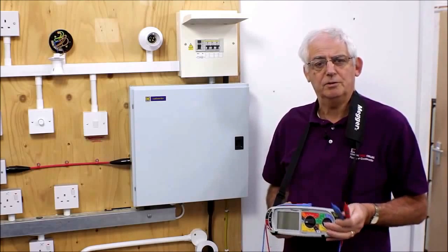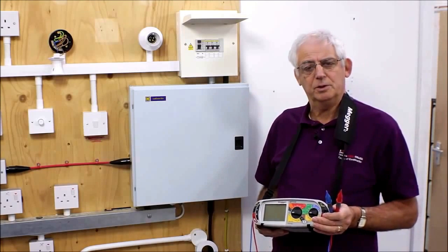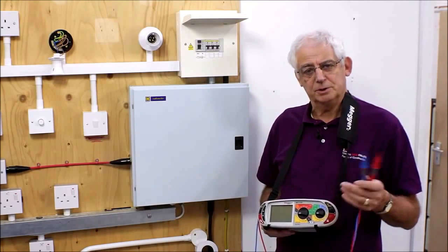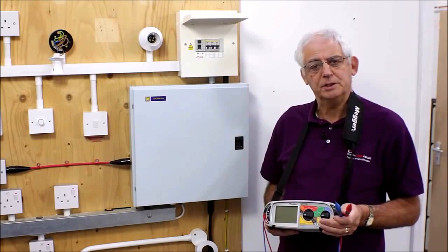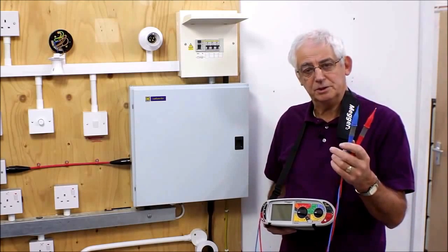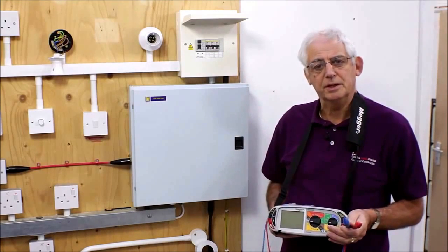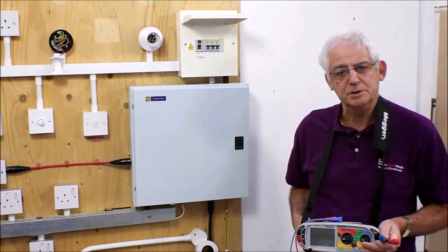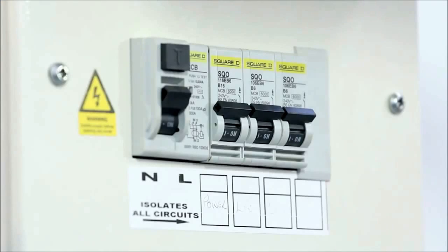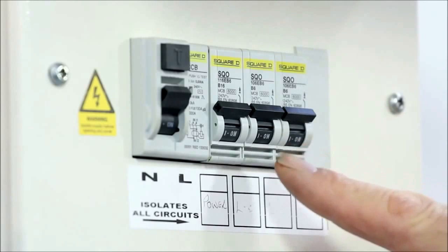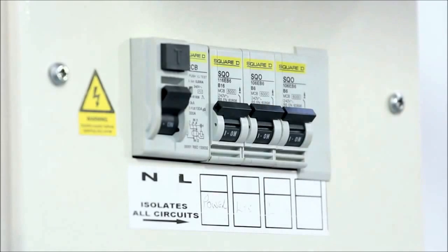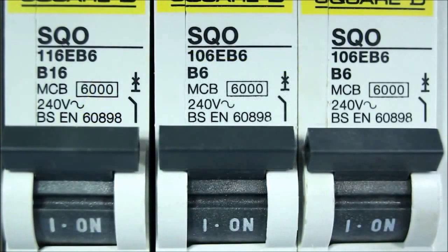Whichever's your choice. Very often the lamps are quite difficult to reach, so sometimes it's beneficial to do it from the switch. And of course, if you're using 2 leads, you don't need the neutral, so that's the benefit of this machine. First of all, I need to look at the protective device, which is protecting the circuit. And for this one, I can see that it's a type B 6 amp BS EN 60898.